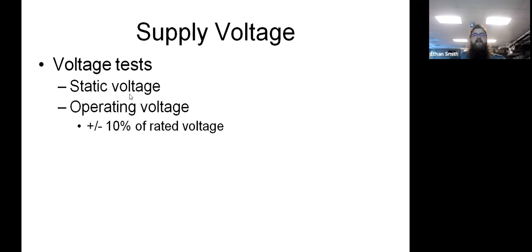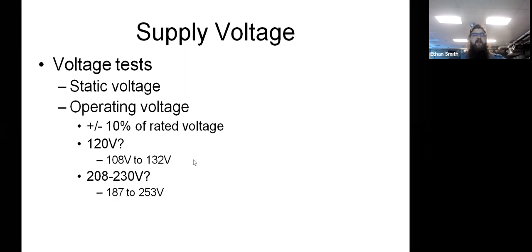If you're in a 120 volt circuit, that's going to be plus or minus 12 volts, which works out to your operating range for that unit is 108 to 132 volts. Outside of that range, we've got a problem that's got to be addressed, because it's going to destroy equipment at that point. 208, 230, your range is 187 to 253. When you're going out and doing maintenance on stuff, you should be checking your line voltage to your equipment.